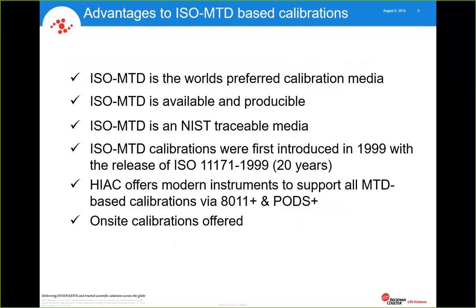So, ISO medium test dust, it's the world's preferred calibration media. It's available and reproducible. It is a NIST traceable calibration media rather. The medium test dust calibration was first introduced 20 years ago with the first release of the ISO 11171 standard. The 11171 standard is a calibration standard that can be used across the world, and if it's adhered to verbatim, then it doesn't matter who the manufacturer is of a particle counter, as long as they're using the right calibration media and all the annexes within the standard, you're pretty much going to get a particle counter that's going to read out. They're going to track pretty closely, even by different manufacturers, as long as they adhere to the standard.